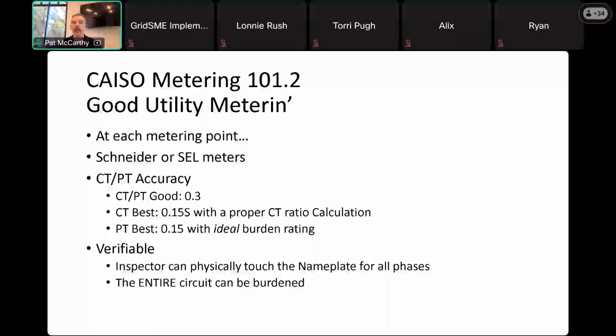is, depending on what year of ANSI standard you're looking at, good for anything from the nameplate rating of the CT, or 90% of the nameplate, or sometimes down to 10% of the nameplate, through the rating factor of the CT. It's a little bit technical, and you don't really need to know any of that right now, but the point is that the S means extended range. There is an accuracy class which will give you that range of accuracy all the way down to 5% of the nameplate rating of the current transformer, with proper ratio calculation.